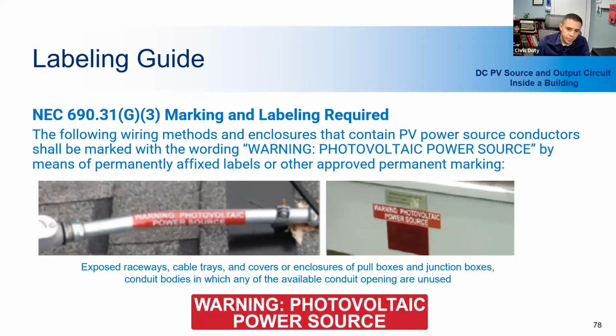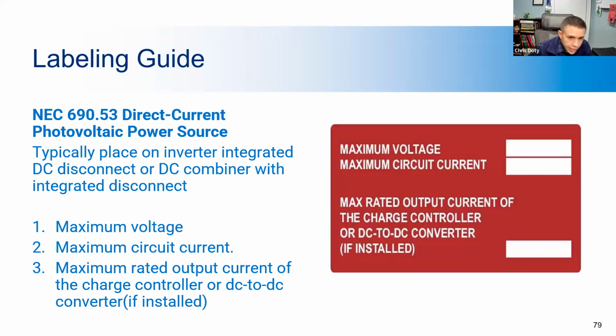Also, something to keep in mind is if they do run it through the attic with the DC power inside it, they still have to have this label on it. You just won't see it because it's in the attic. Here we have a direct current PV power source label, which must be on an inverter integrated DC disconnect or a DC combiner with a disconnect. This gives important information on the system for anyone who will maintain and repair the system in the future. You have to label the max voltage and the max circuit current. And if you have a battery system installed with it, you want to have the max current of the charge controllers as well.